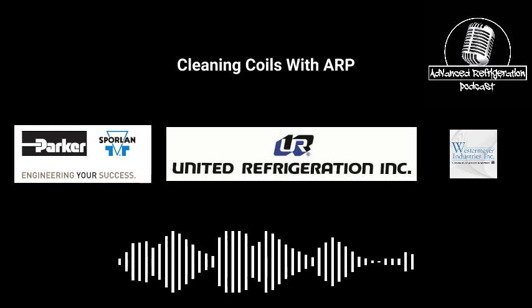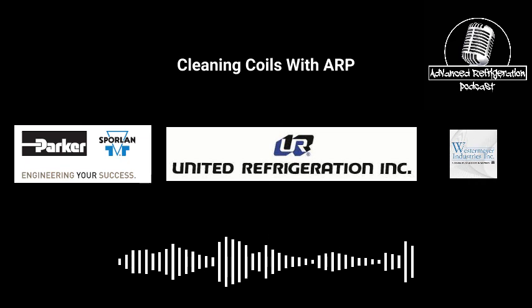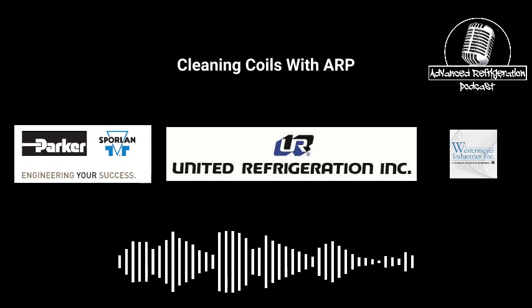So the reason I push it in is because it makes less of a mess when you're cleaning it, because it's going to hit the fan blades, and maybe a little bit will come out the fan guards. But if you do it the other way around and you're pushing it through the back, it's going to be spraying down the back wall of the cooler. It's going to be getting on the product, even plastic there. So it's easier to control it going into the evaporator. Then you could rinse out the drain pan, then pull the fan blades and clean them.